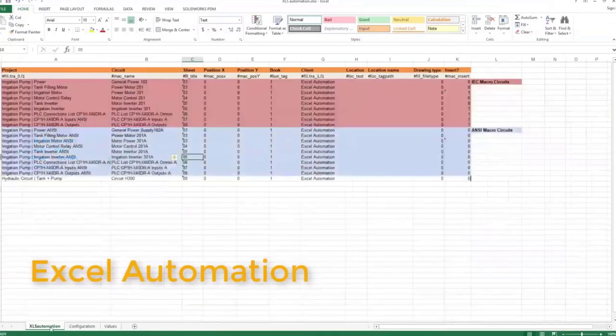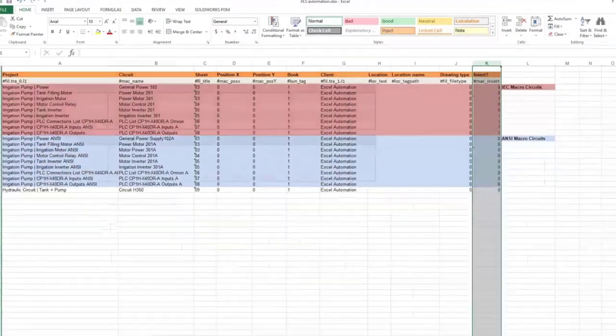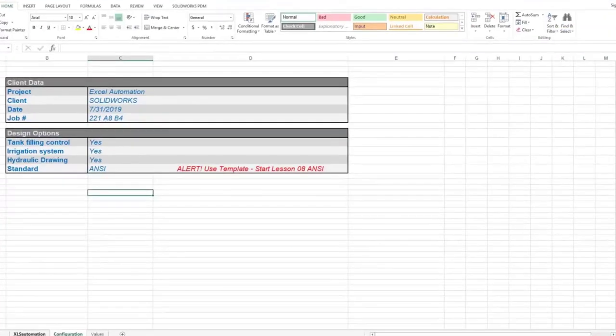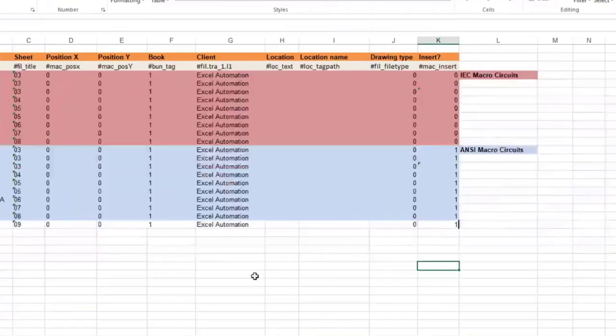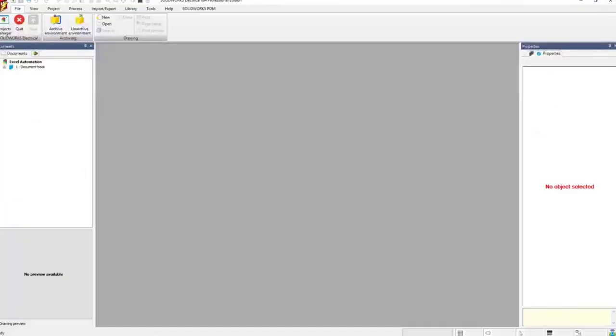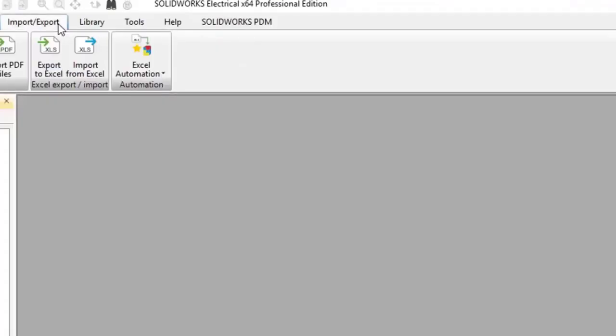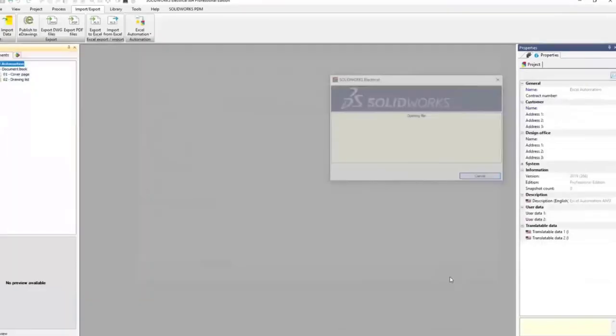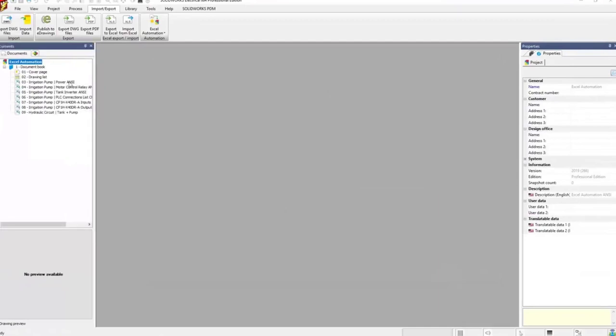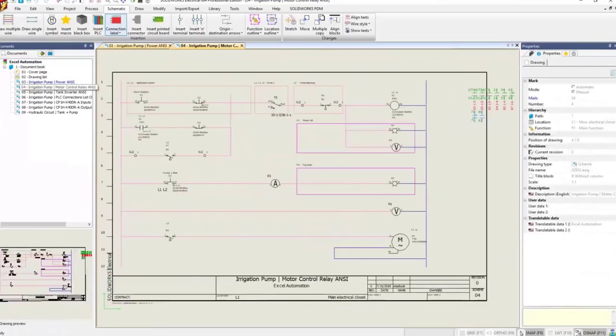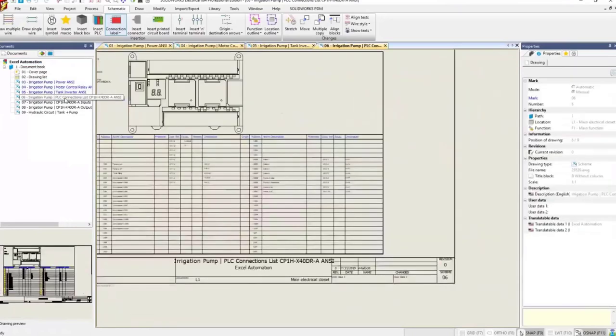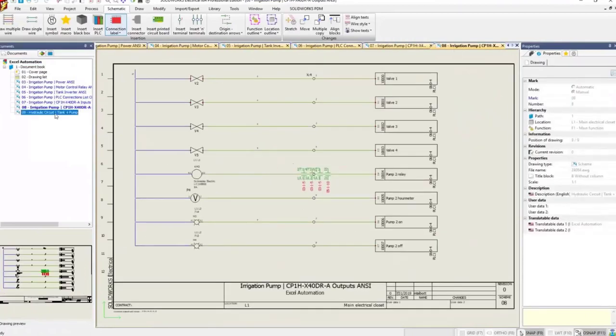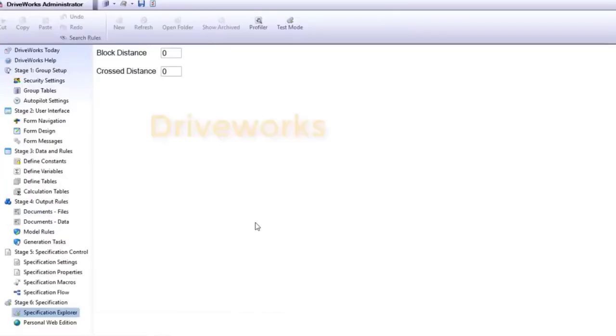So now we want to push the envelope here. What we're going to do is incorporate something called Excel automation. In other words, what we did with the PLC tool, where we configured a table and generated the schematics, we can actually do for an entire project. So in this case, I'm going to fill out a form. That form is going to make all the changes I need for my project. So I've got a base design. I fill out inputs from the customer. They want a four motor system. They want to use this PLC. They want this kind of cable on the output. And I can point to that configured Excel sheet in an empty project. It will draw my entire project for me. This entire project came based on filling out a form. If I delete these schematics, fill out that form differently, and re-import it, I will get those changes. Very powerful tool. Configure to order for your schematics already built into SOLIDWORKS Electrical.